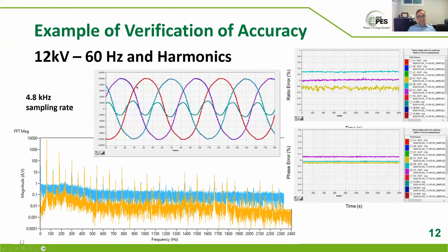And in this page, you can see the overlap of the synchronized waveforms. It's hard to see, the overlap is very good. So the dotted and the not dotted waveforms are from the reference and the device under test. We are also showing in this case the summation of the three voltages, or zero sequence if you want to call it. There is a significant amount of third harmonic, right? You can see basically about 25% summation of the three, or each of them about, I don't know, 8-9% third harmonic, because it was a feeder that was very, very lightly loaded, and you would expect the transformer to have a good amount of third harmonic.